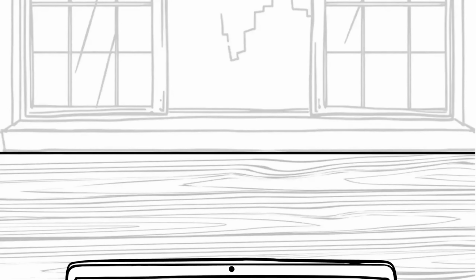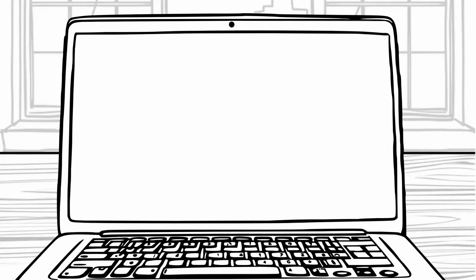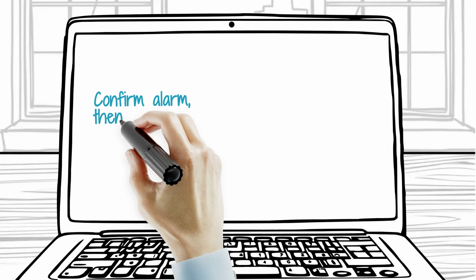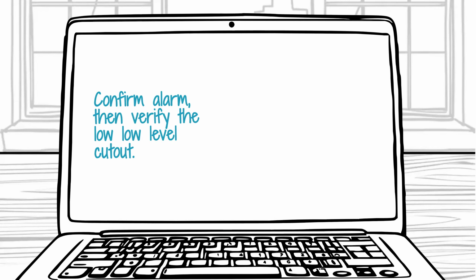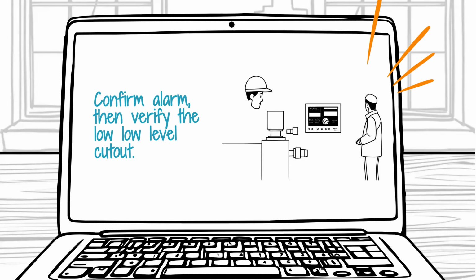Once the low-level alarm is confirmed, you must continue the test to verify the low-level cutout, which is the final safety that shuts down the burner and closes the fuel oil quick-closing valves. This second stage of protection prevents the boiler tubes from overheating and melting when the water disappears.